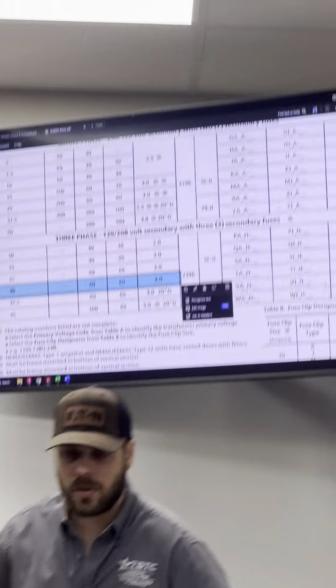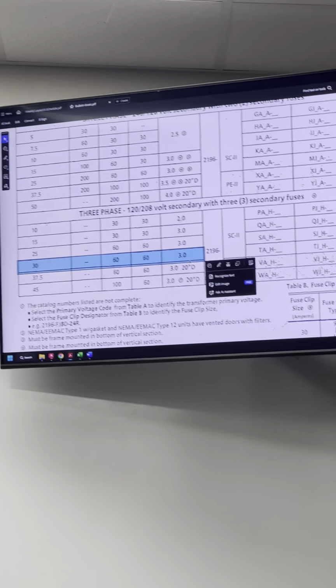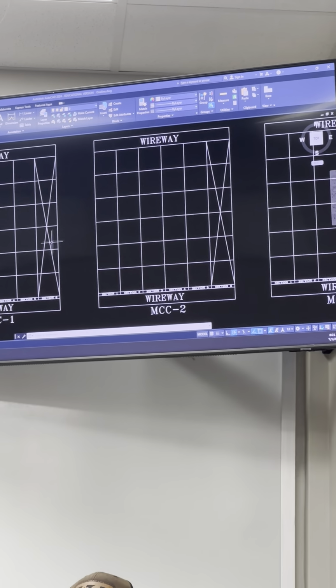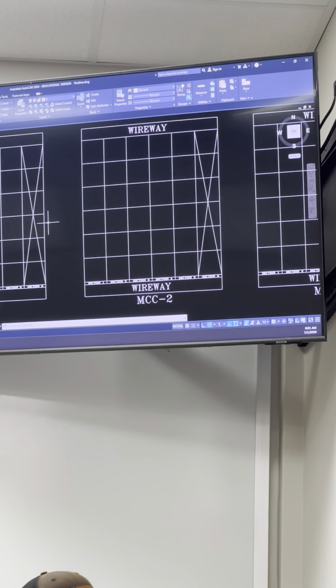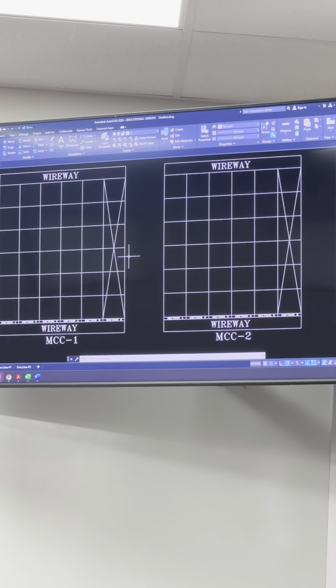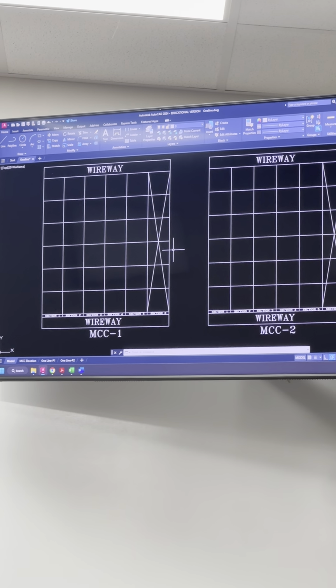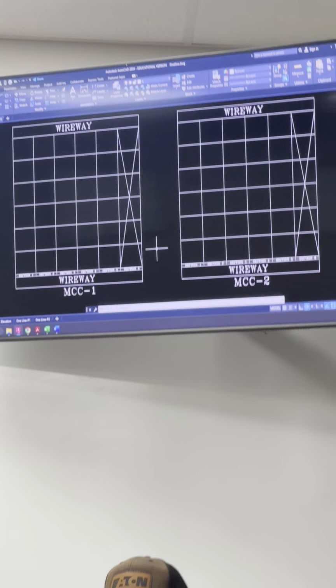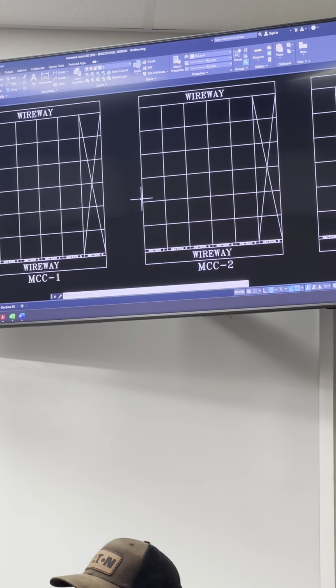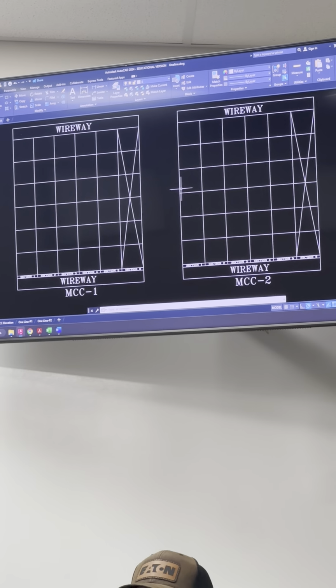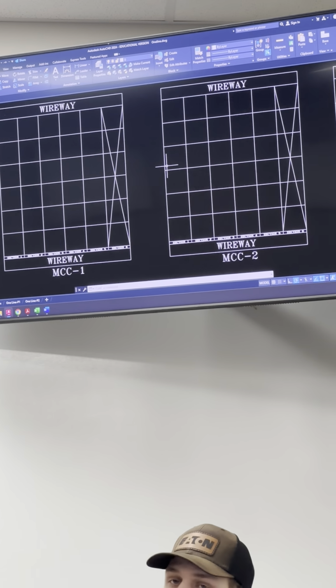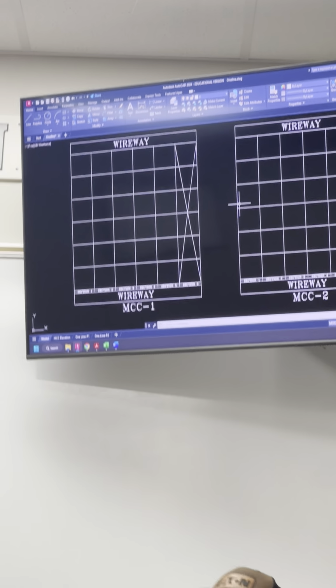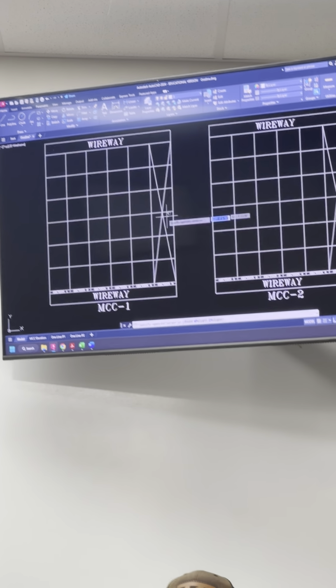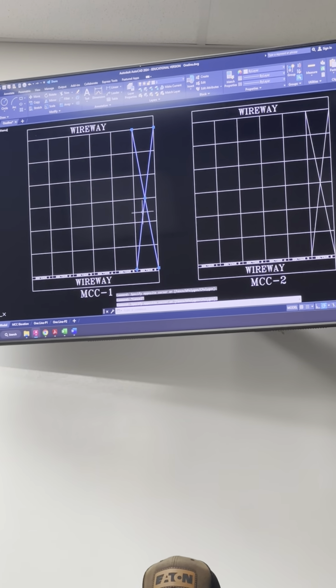However, there is the drawing portion of that, and we will cover that real quick. So on the one line, on your MCC elevation here, you should still have that section 6 blocked off. Of course your MCC should be filled in—mine's not, because I don't save that work. But in section 6, this is now where we're going to install both the transformer and the panel. So we can go ahead and get rid of these cross marks.